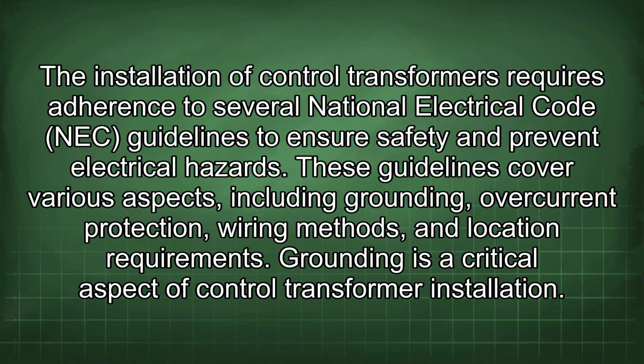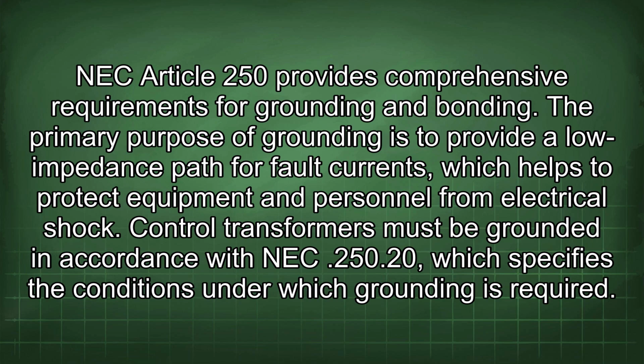The installation of control transformers requires adherence to several National Electrical Code (NEC) guidelines to ensure safety and prevent electrical hazards. These guidelines cover various aspects, including grounding, overcurrent protection, wiring methods, and location requirements. Grounding is a critical aspect of control transformer installation. NEC Article 250 provides comprehensive requirements for grounding and bonding. The primary purpose of grounding is to provide a low impedance path for fault currents, which helps to protect equipment and personnel from electrical shock.